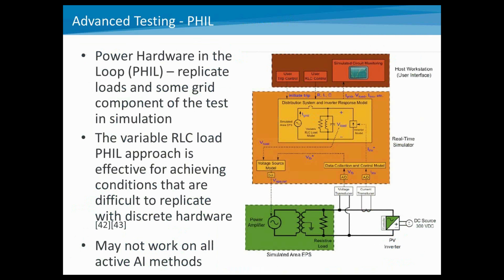And some of the things that we've worked on include improving those tests. One of the very big challenges is when you have a large scale singular device, like a megawatt or greater than megawatt, you need an RLC load bank that has all of those components rated at that power level. And one of the things that we did was some advanced testing looking at whether we could replicate the load bank and grid conditions in what we call hardware in the loop, or power hardware in the loop.